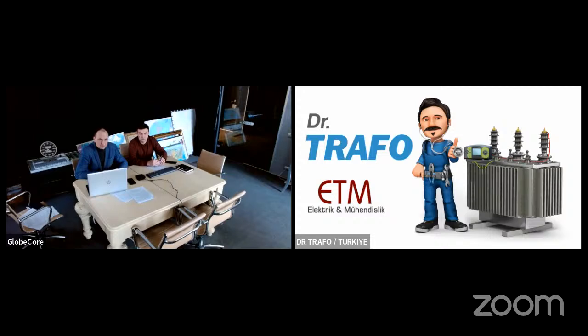It's not GlobeCore, it's from another brand. But one of the observations I've had is that when you do oil regeneration, the breakdown voltage becomes perfect, all the conditions become very good.